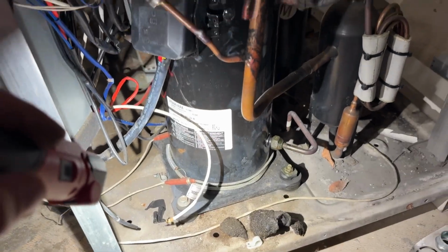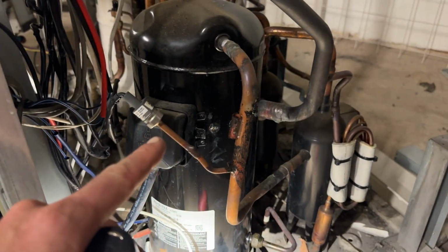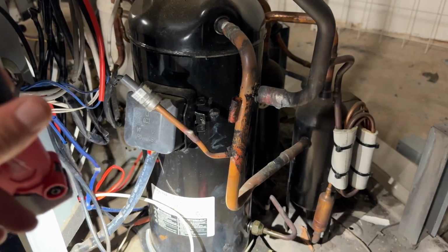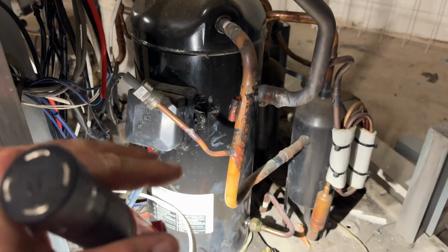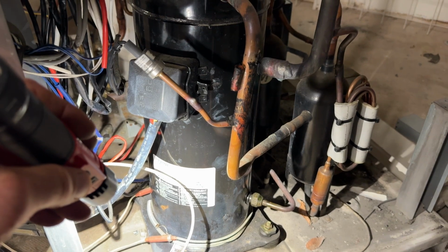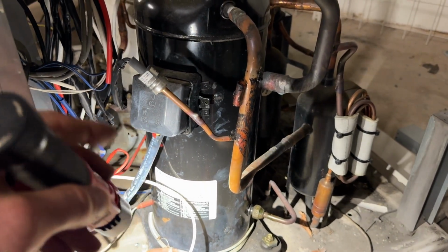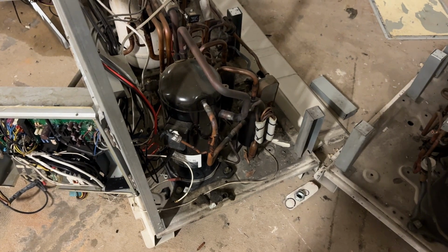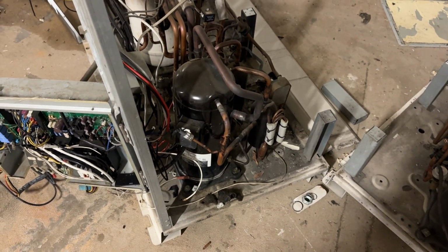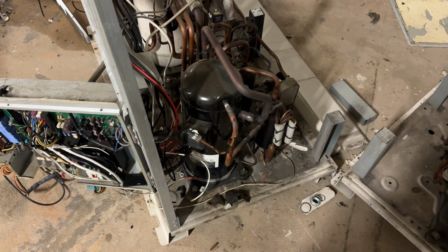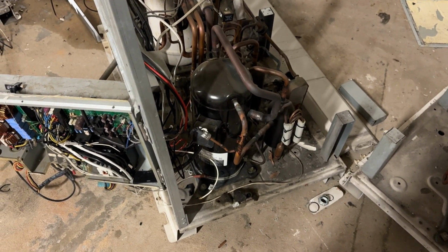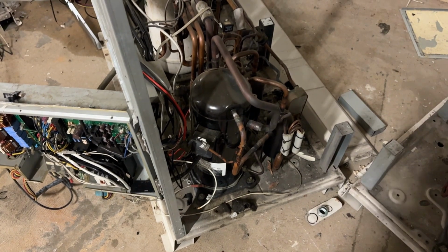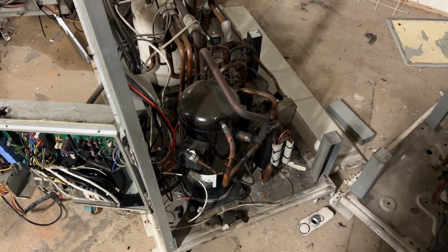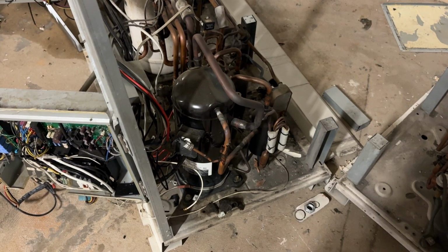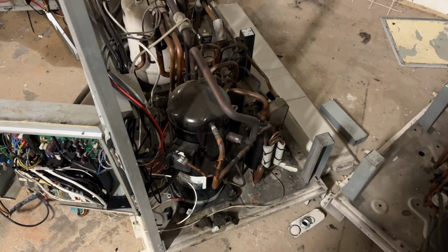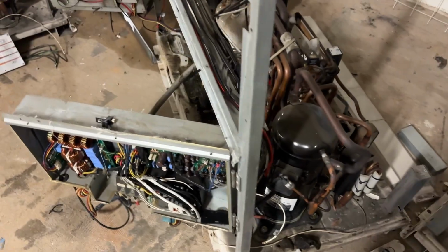This is a crankcase heater, and you have to be careful condemning these compressors if it's cold out and the unit has lost power, because as these compressors fill up with liquid, they will show a bad meg reading. Copeland has actually released a bulletin on their compressors stating that if you have liquid in the sump, you can read with the megger, like, I think it's half a mega ohm, so 500,000 ohms, and the compressor's still good. It's just liquid in there. So you got to be careful with that.